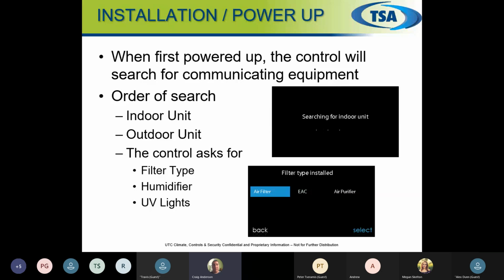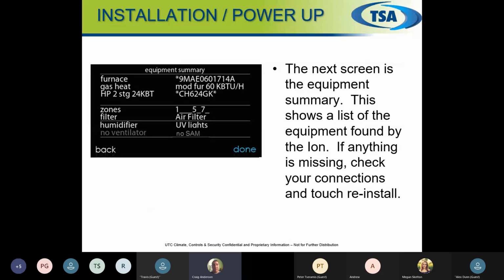So once it finds your equipment, it's going to tell you, this is what I have hooked up. I have a G9MAE060. Here's your model number. It's going to tell you that I have a heat pump hooked up to it as well. So it's going to give you a summary and you're going to say, yes, okay. Or you're going to say, hey, search again. You've missed something. If it's missed something, do a search again. If it misses it again, then we have to go back and we have to look at some wiring. Something's not plugged in correctly. Very uncommon for the unit not to find the outdoor unit if the plug is in there. Very uncommon.